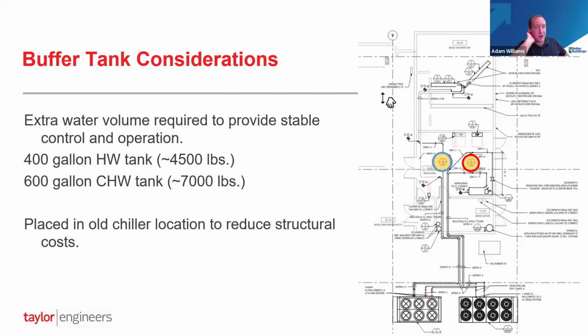The other thing with these heat pumps is that they generally require a lot of water volume in the system for stable operation to avoid turn down issues and other things. For example, when these run in a defrost cycle, they're going to spend a few minutes each hour running the wrong way, running as a chiller rather than a heat pump, and they want to have a sufficiently sized buffer tank so that they can provide stable temperature control even during those defrost cycles. Buffer tanks and system volume requirements are common for all chillers, right? But these heat pumps can sometimes require a lot of system volume. And also some of these heat pumps like primary-secondary piping, which means that you don't get to utilize as much of the building pipe as you would like for the system volume.